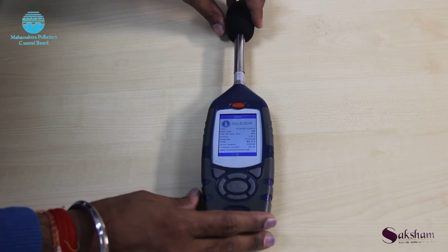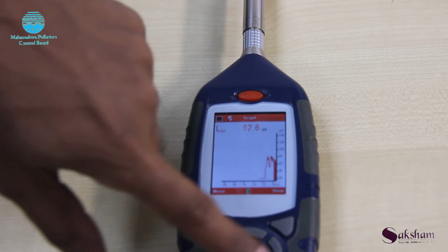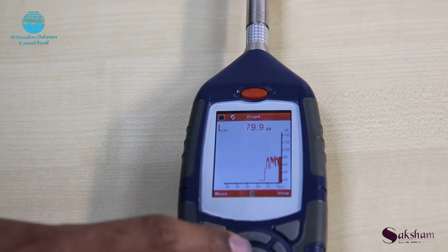Now we will check how to take a reading by using the sound level meter kit. We first calibrate the instrument by using the acoustic calibrator. Then, after doing the calibration, I have to insert this windshield on the microphone. So this is the home screen. On this home screen I have to start taking a reading. On the navigation keys at the center, one pause play button is there. To start taking a reading, I just press that middle key, so that the red colored screen changes into the green color.